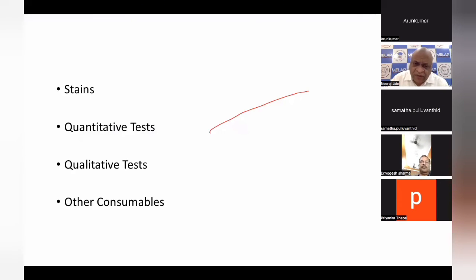And if you want to be more confident about your lot acceptance testing, you can perform the same activity with one patient sample also. This is for your quantitative test. For this, what is required? The laboratory shall have documented procedures for how they will carry out lot acceptance testing. Then, lot acceptance criteria. What is your criteria? How are you accepting? So you are saying within +-2 standard deviation.